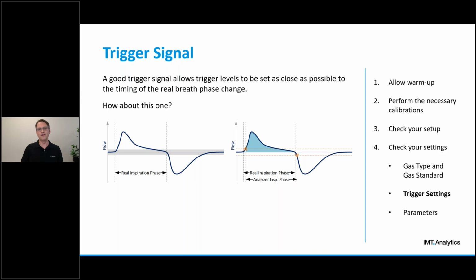What does that mean? For our timing parameters like inspiration time or a rate measurement, it doesn't have significant impact because it's just a little bit shifted in time, right? But as we have seen in one of the previous slides, this is going to have a little impact on our volume calculations. Because if we take a look at the inspiratory tidal volume, for example, which is that shaded area underneath the flow curve, we are going to miss a little bit at the start of the inspiration phase. And then it's going to consider a little bit of our exhalation flow already still in our inspiration time. So that means it's going to be deducted from our volume calculation, which leads to the fact that our calculated tidal volumes here are not going to be 100% accurate. So overall, we can say that this is a quite good trigger signal, even though it could be even better if the slopes of the waveform were steeper at the beginning of the two breath phases.